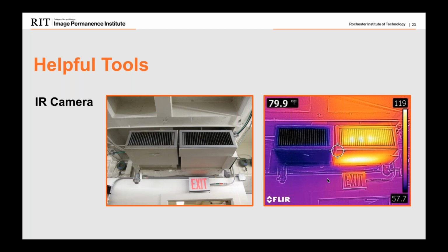These two images here, the one on the left is what you saw walking through the space, just what you observed in the collection area. The other image is what we saw as we imaged everything with the infrared camera. Though the space was close to temperature, what we saw was that a reheat had failed, and every other vent in the space was served by that one reheat. One side of the air handling unit was supplying cold air and the other side was supplying warm air, so the unit was literally fighting itself to condition that room.